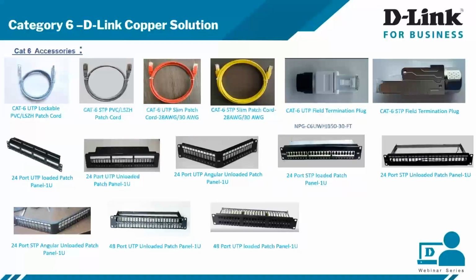For example, if you use a 90-meter solid cable with a 5-meter regular patch cord to make a 100-meter channel, in this case with the 28 AWG patch cord, following a de-rating factor of 6 meters with a 90-meter cable, you would use only a 3-meter patch cord. So instead of reaching 100-meter channel length, you get a 96-meter channel length.